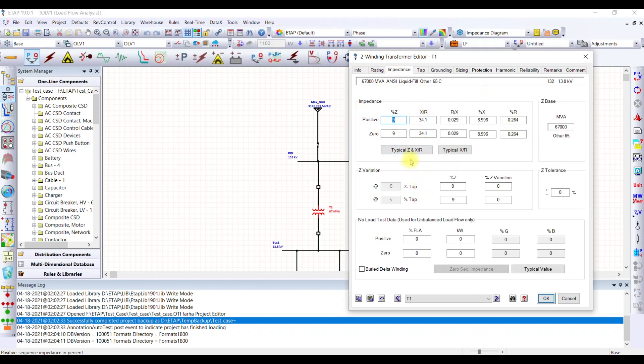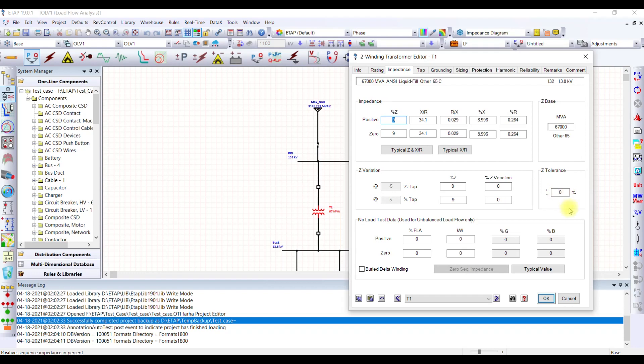Typical values will provide you with whatever the impedance value is going to be there for a certain type of transformer. If you want to consider some tolerance, you can select the tolerance level from here. What will happen is that it will consider this tolerance while performing the analysis. This is important because if you don't know the data, you want to go with the worst case scenario. For load flow analysis, worst case scenario is more impedance because higher the impedance, the more will be the voltage drop.